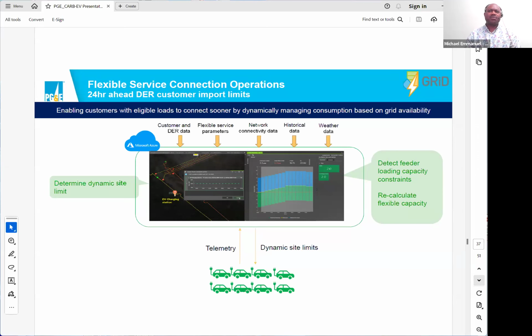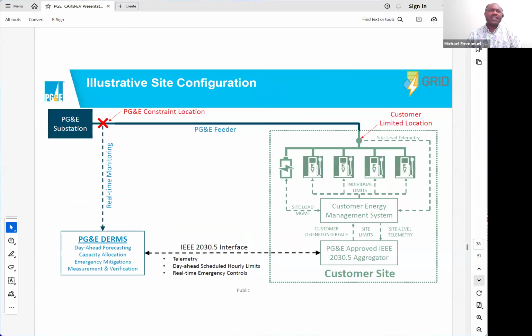Let's go to the next slide. This gives me the opportunity to talk about the architecture — this is the site configuration. On the left-hand side, in this case, the feeder is what's being constrained. Depending on where the site is located, there are different types of constraint — it could be at the feeder head, at the bank level, or even a line. Any of these, or a combination, can be the constraint limiting the customer from coming online.